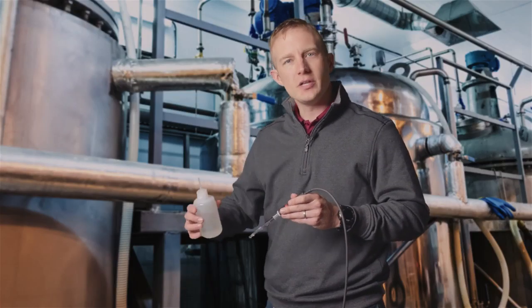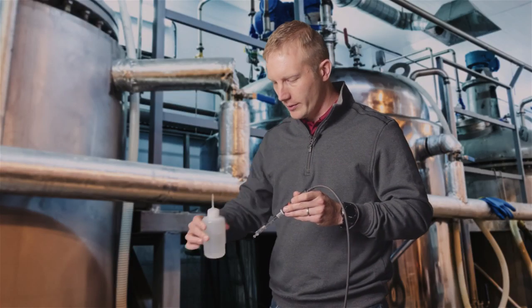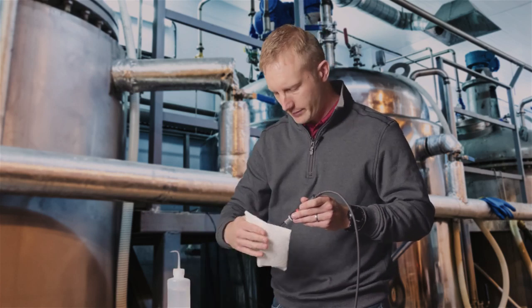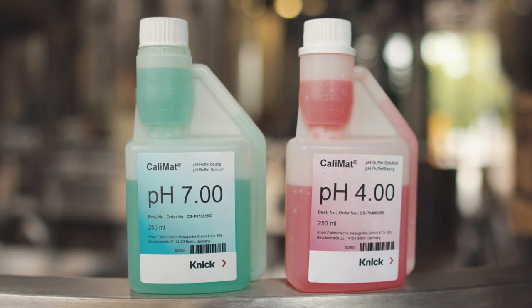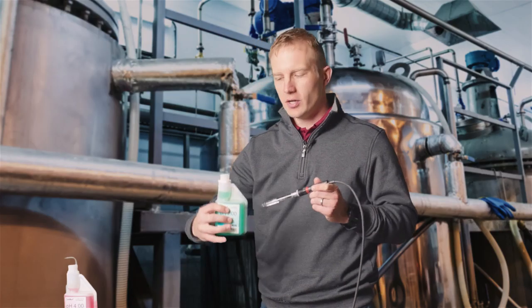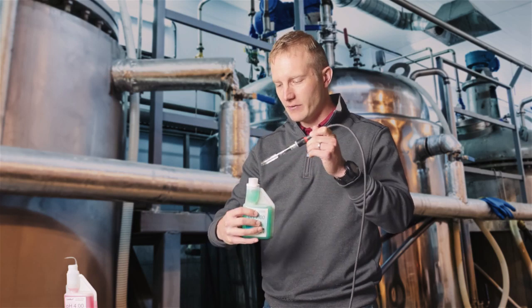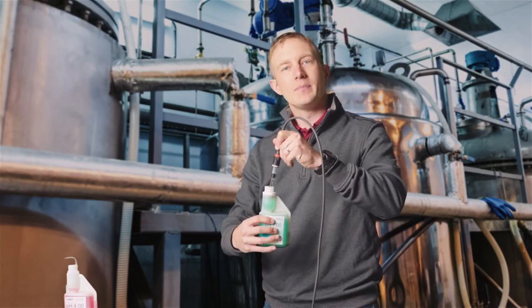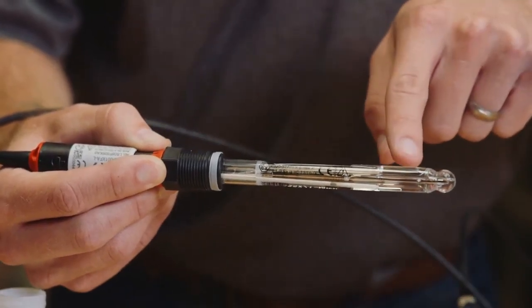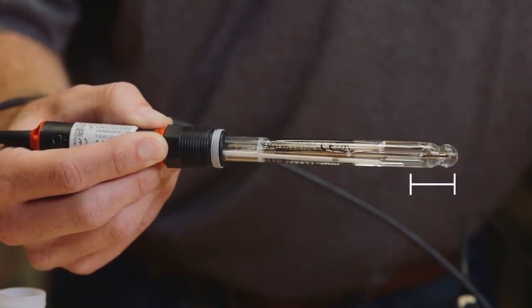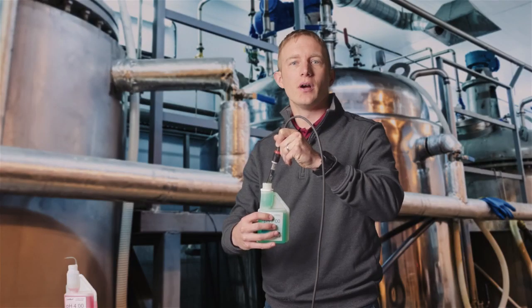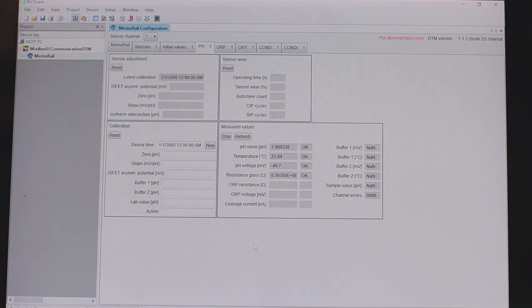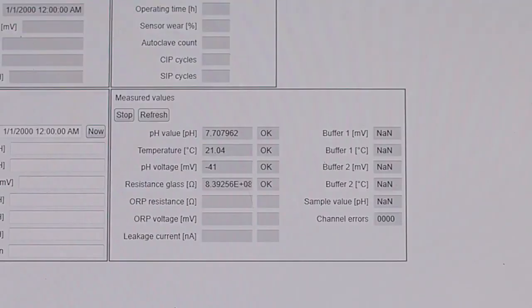First, ensure that you rinse your sensor with distilled water and then dab it dry. For this calibration, we'll be using pH buffers 7 and 4. Let's begin by placing our pH sensor in buffer 7 and stirring lightly. As always, we want to ensure that the entire pH bulb as well as the sensor's junction are completely immersed. We can see on our DTM screen that our measured value is changing.